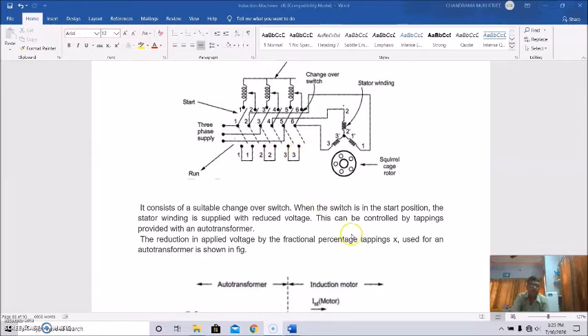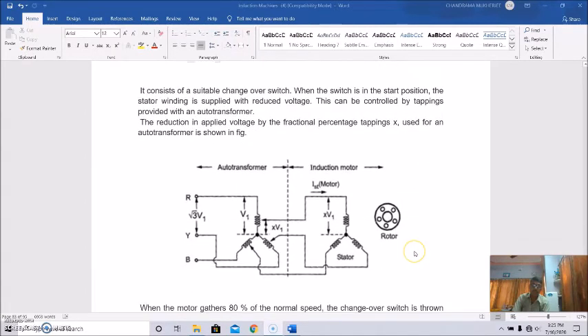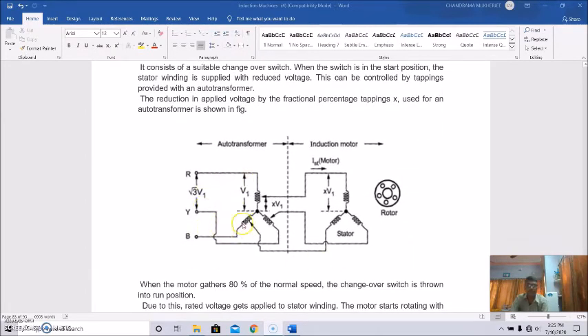When the switch is at the start position, the stator winding is supplied with reduced voltage, and this can be controlled by the tappings provided on the auto transformer. Different tappings are provided here. The reduction in applied voltage is by a fractional percentage tapping, say X, used on the auto transformer. This is shown here. This is the auto transformer, this is the stator winding of the induction motor, and this is the rotor.